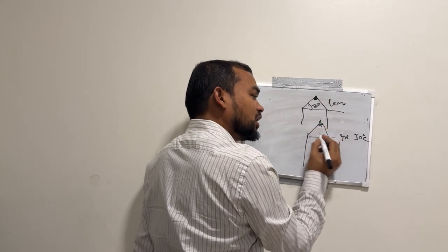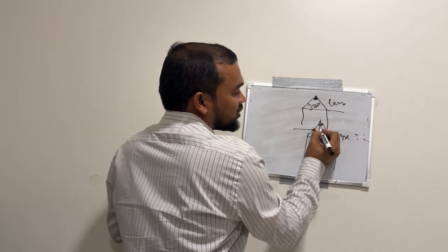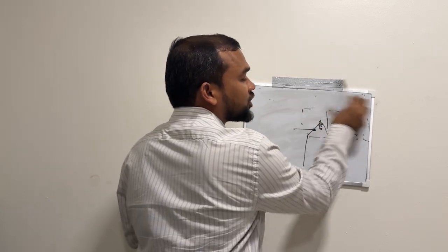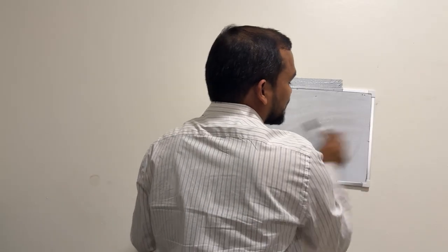The detector will be installed at the peak location, the peak height of this location. In this case, a detector will be installed at the peak of the ceiling. The remaining detectors will be installed at the average sloping height of the ceiling, and all will be covered within 36 inches from the ceiling.